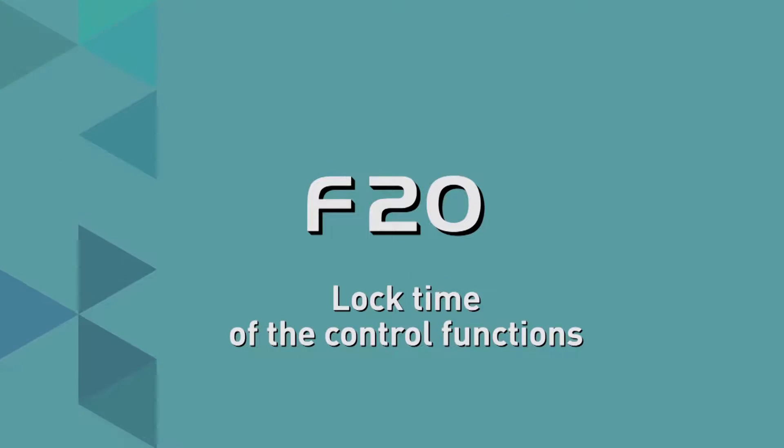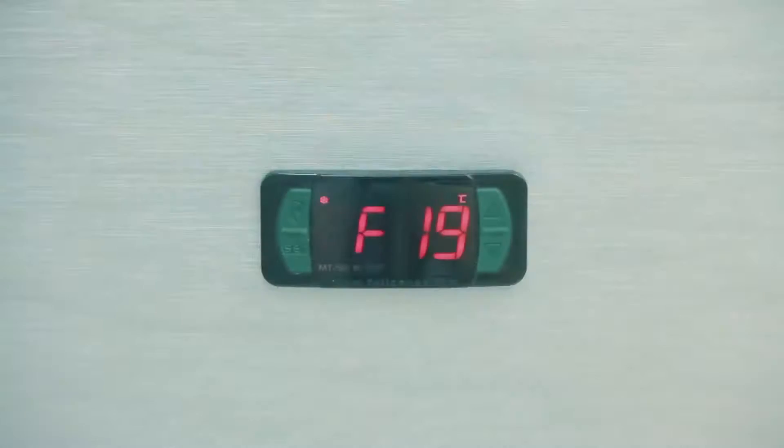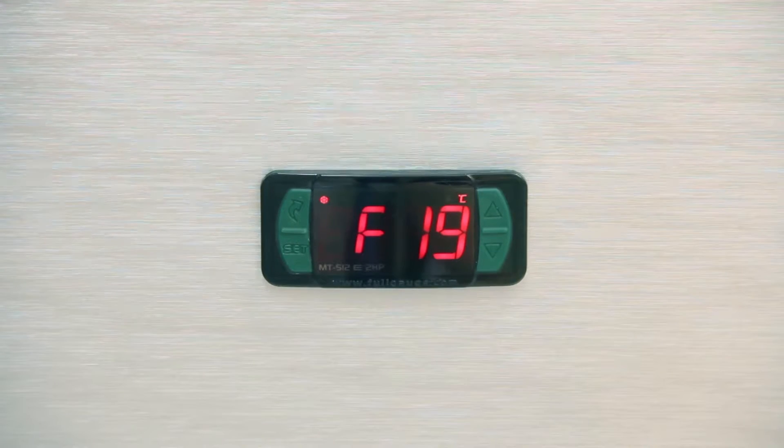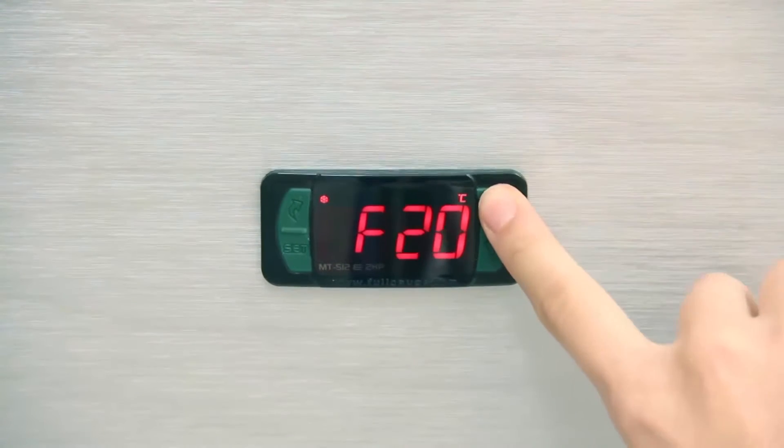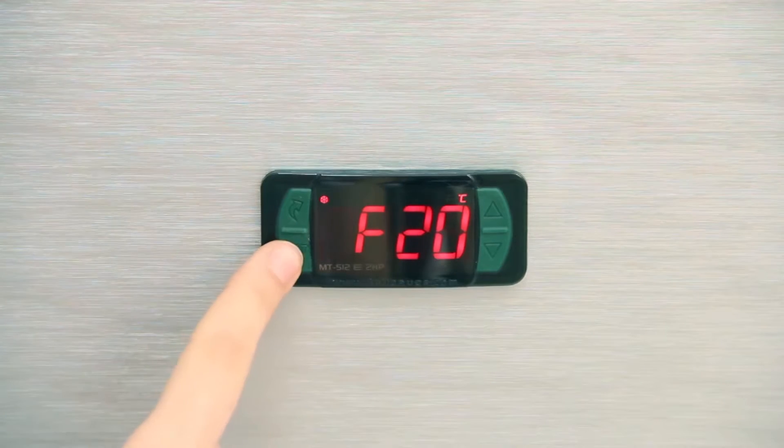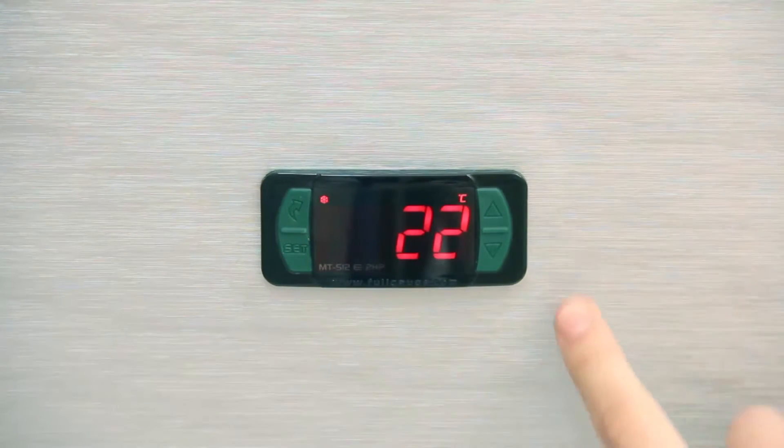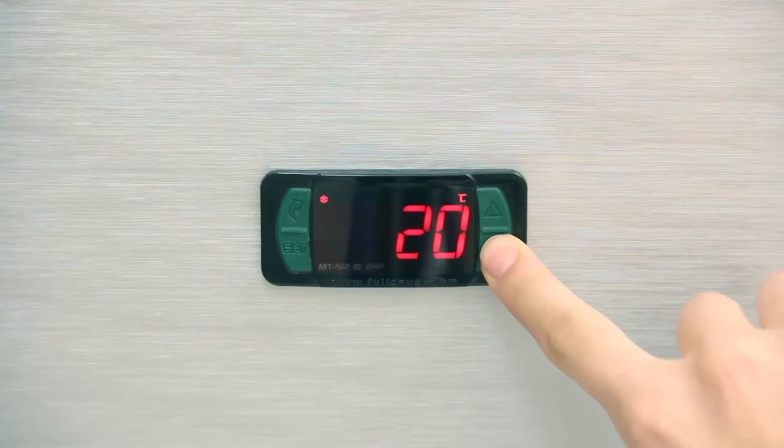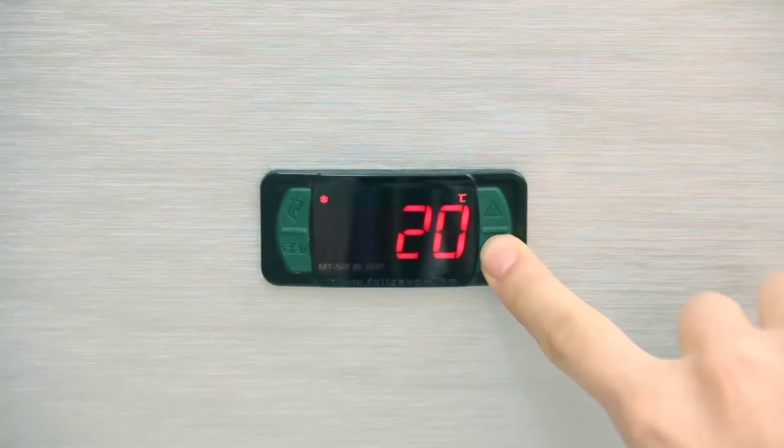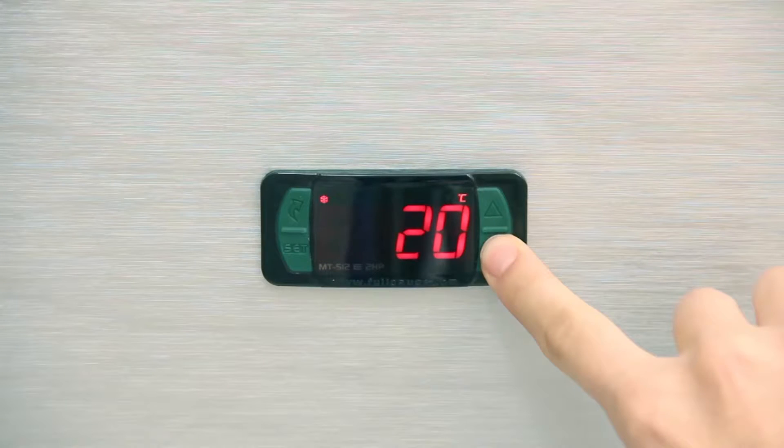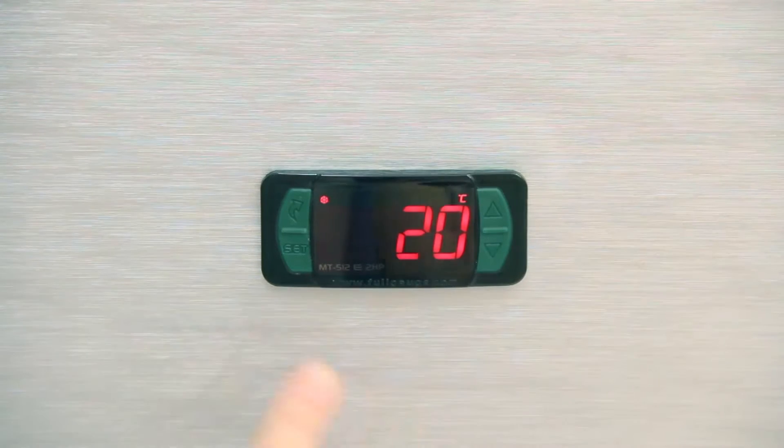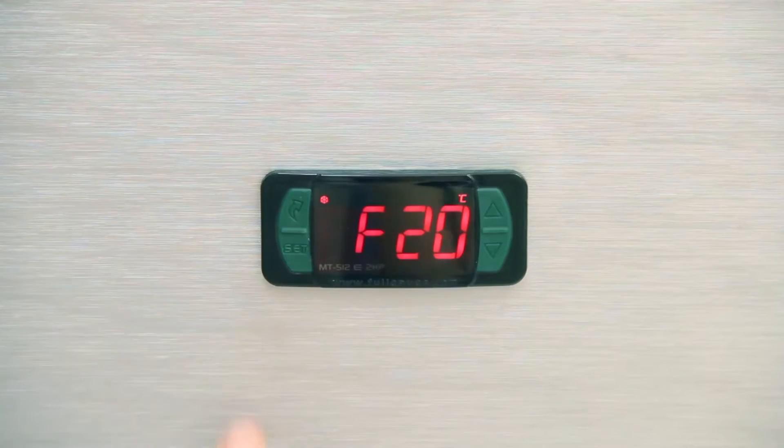F20, Lock Time of the Control Functions. To activate the lock, it is necessary to adjust the F20 parameter with a value greater than 14. For this reason, we adjust the parameter to 20 seconds in the examples. With this activated locking, the set point and other parameters are protected against unauthorized changes. We have seen this function in basic operation.